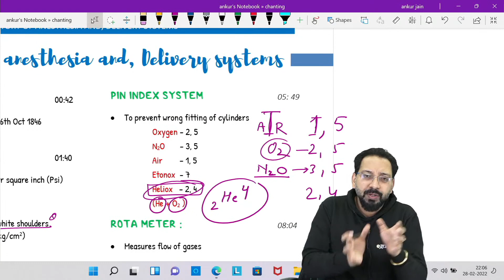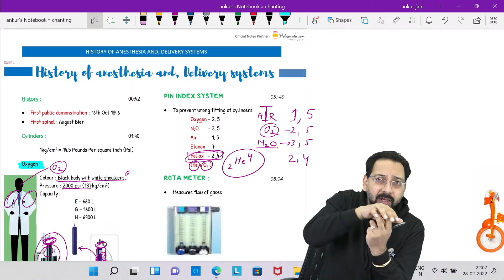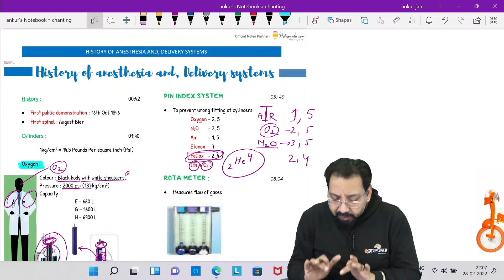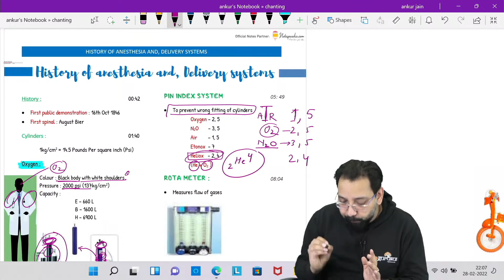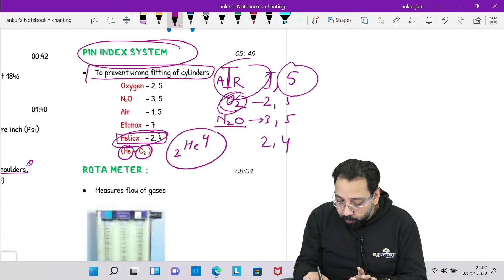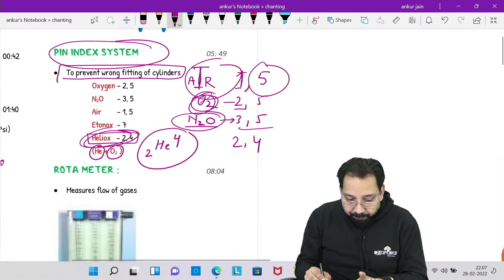What is this pin index? Sometimes you are a doctor, and you are not putting these cylinders on the anesthesia machine. This is the anesthesia machine. We will not put the cylinder ourselves. So we made the pin in the machine and the hole in the cylinder, so that the distance between the pin in the machine and the hole in the cylinder is the same. That's why every time these cylinders will fix at a defined position. So to prevent wrong fitting of cylinders, we have the pin index system. You remember 5 element: air, O2 2 5 and N2O 3 5, heliox 2 4.